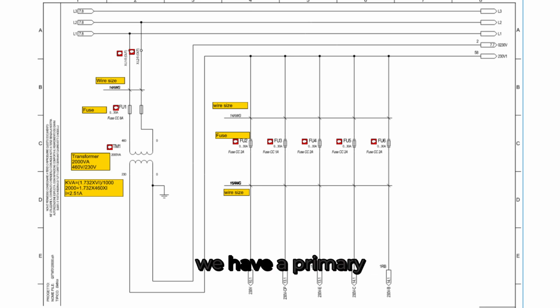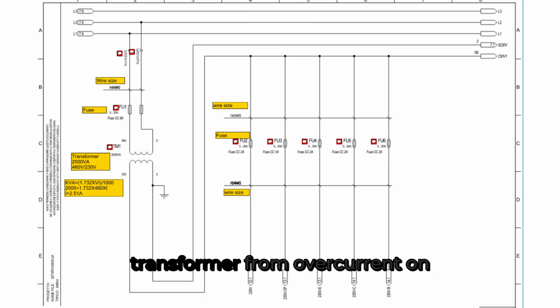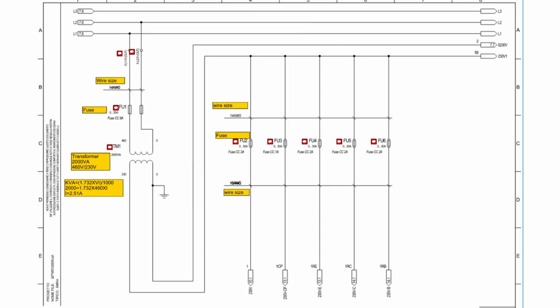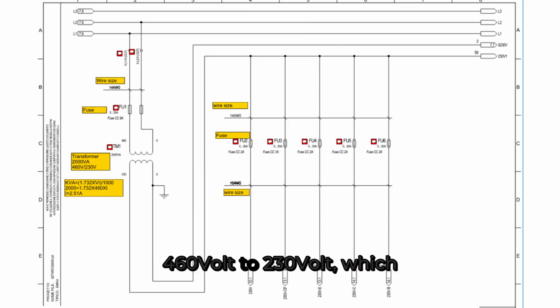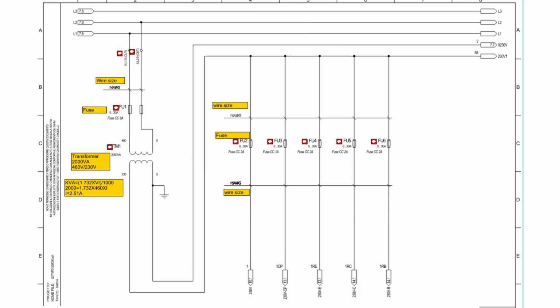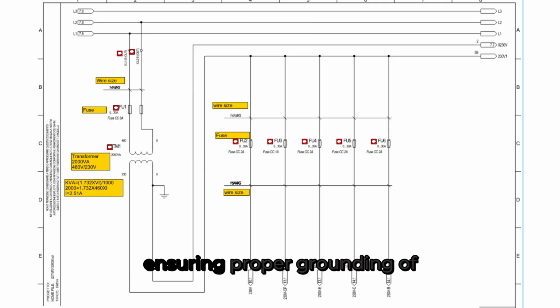Upstream of the transformer, we have a primary fuse labeled FU1. It's a class CC 8 amp fuse that protects the transformer from overcurrent on the high voltage side. The transformer steps down 460 volts to 230 volts, which is then distributed through multiple secondary fuses for different control loads. These secondary fuses are labeled FU2 through FU6, each rated between 1 amp and 2 amps. The outgoing wiring from the transformer secondary to these fuses uses 16 gauge wires, while the upstream conductors from the main terminal block are 14 gauge wires. You can also see the ground connection at the transformer's secondary side, ensuring proper grounding of the low voltage circuit for safety and noise reduction.